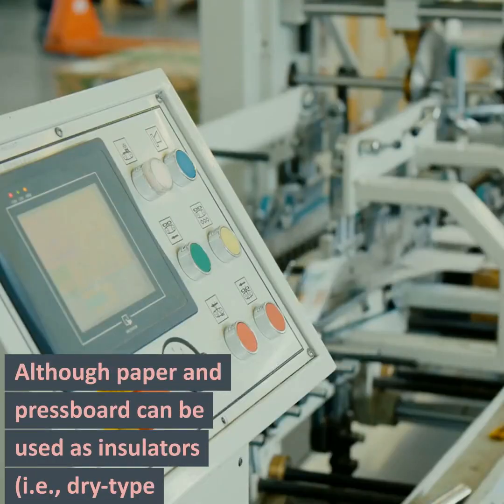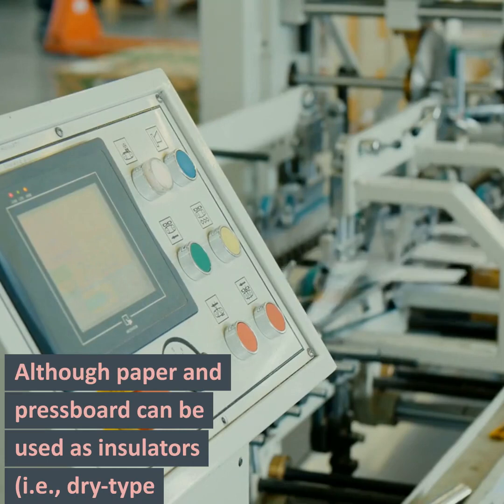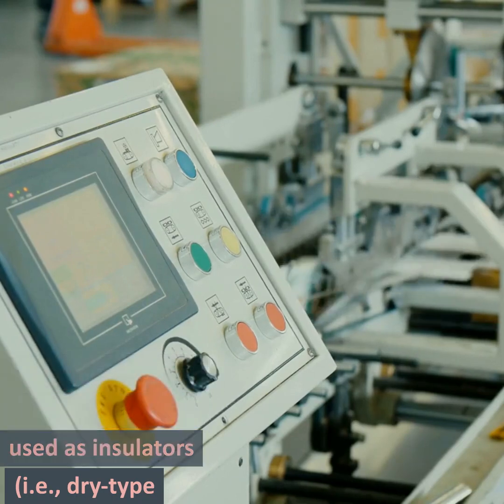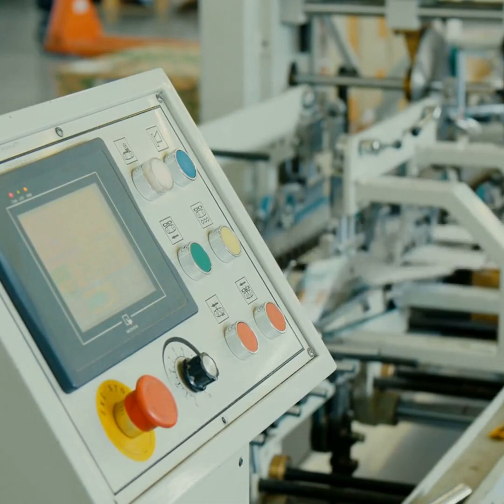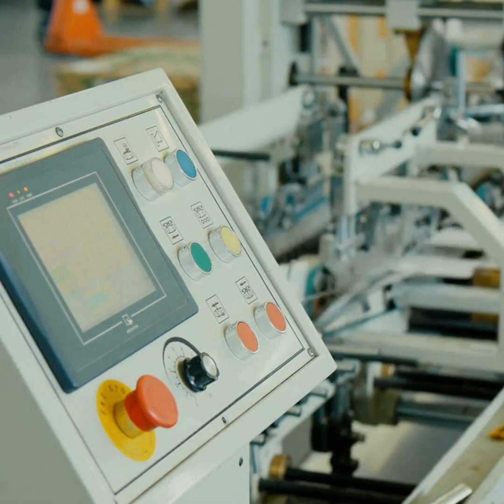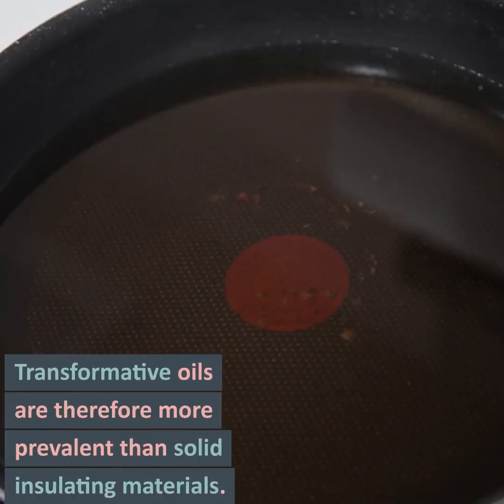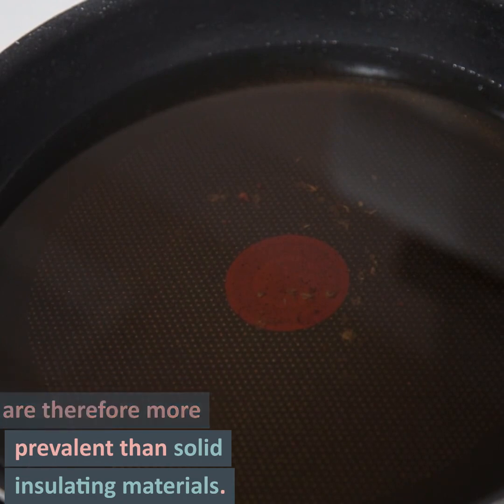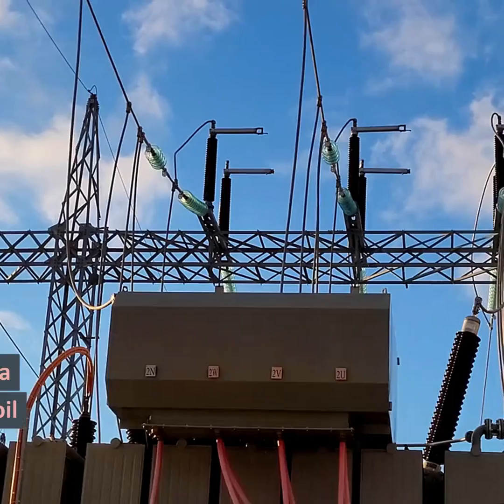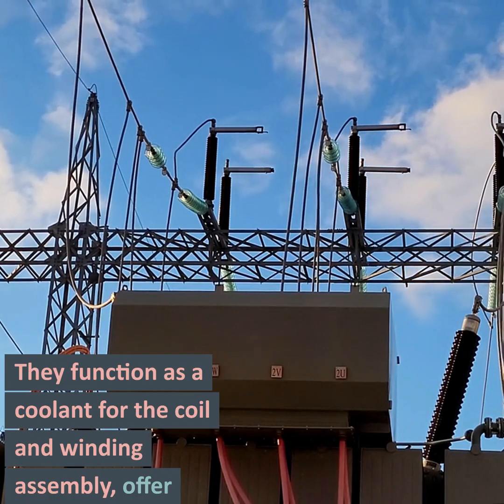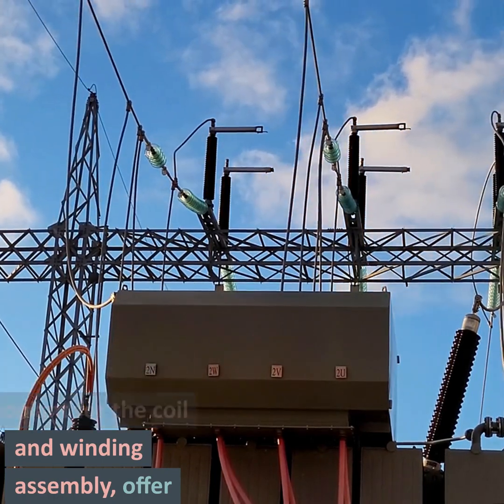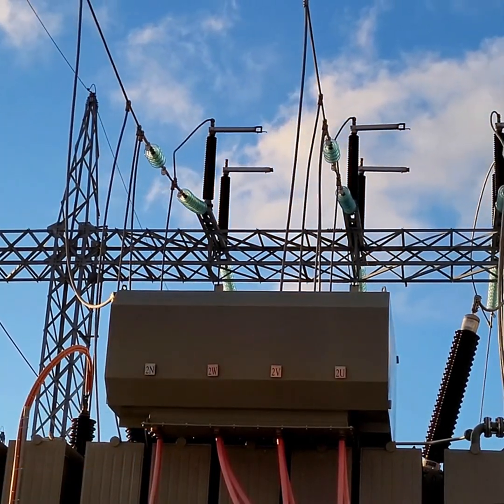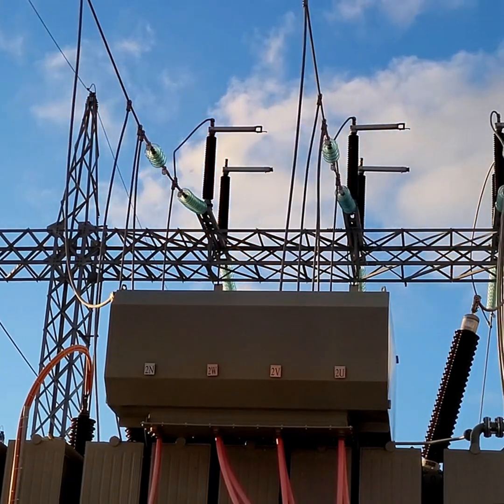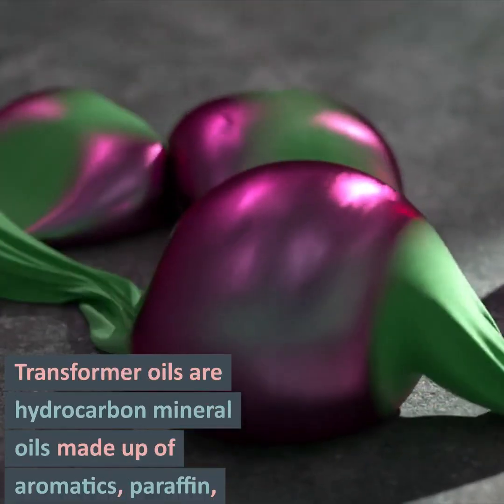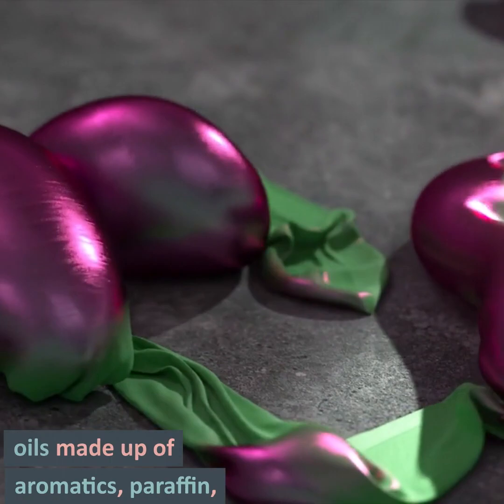Although paper and pressboard can be used as insulators, i.e., dry-type transformers, their service lives are constrained and they need to be replaced frequently since these materials might deteriorate. Transformer oils are therefore more prevalent than solid insulating materials. They function as a coolant for the coil and winding assembly, offer improved insulation between conducting elements, and contain fault detection features. Transformer oils are hydrocarbon mineral oils made up of aromatics, paraffin, naphthene, and olefins.